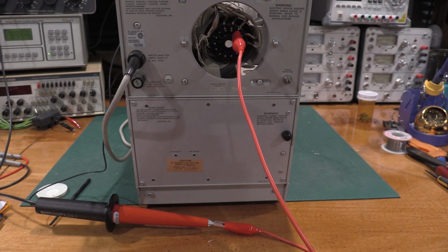We are actually slightly out of adjustment on that. No, we're in just barely, because it's saying at the low side it should be 3230, at the high side it should be 3570, and the meter's giving me 3425. Oh, so we're right where we should be. So high voltage actually doesn't need adjustment, but we'll adjust it just to top it off.